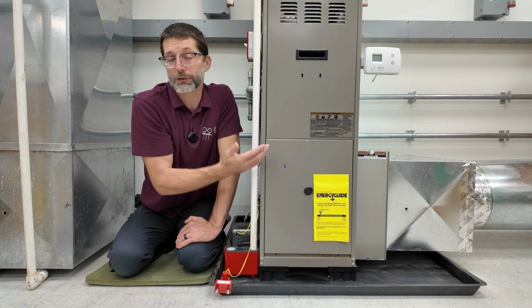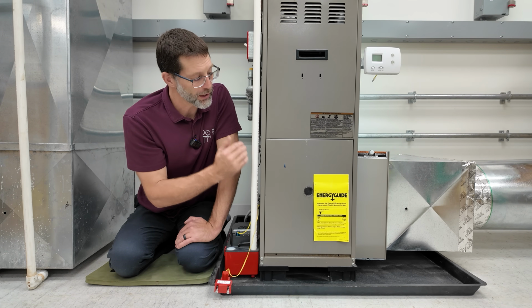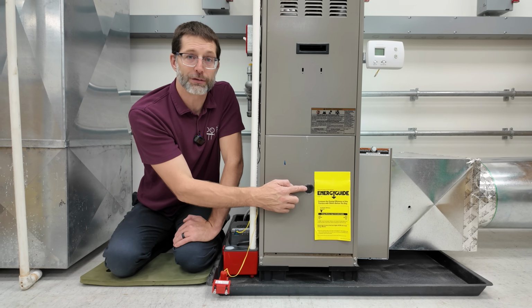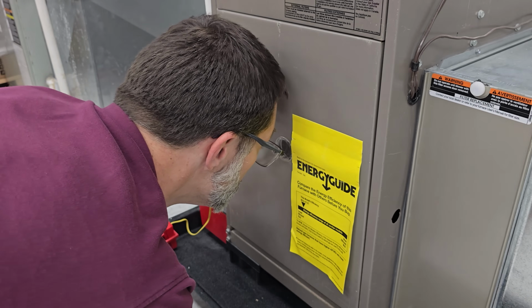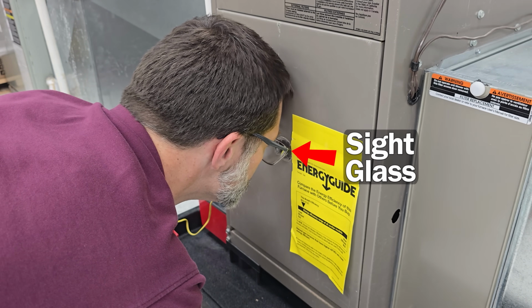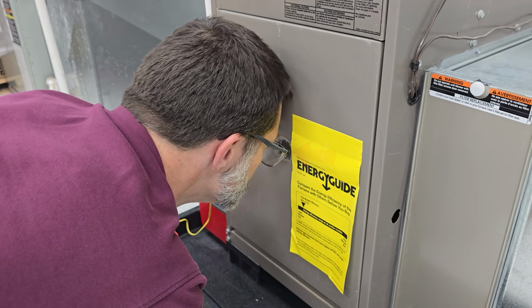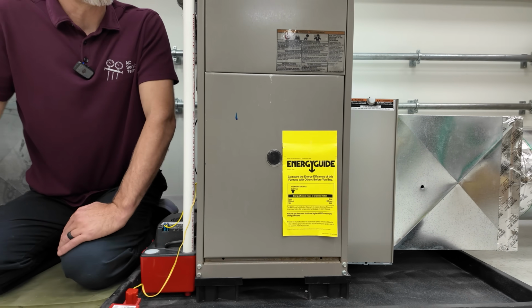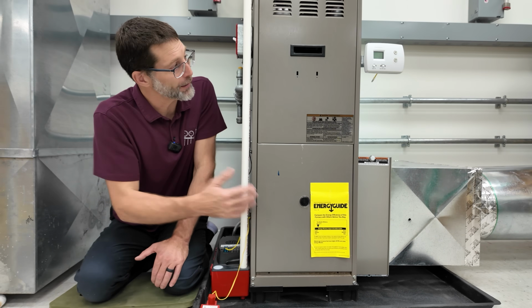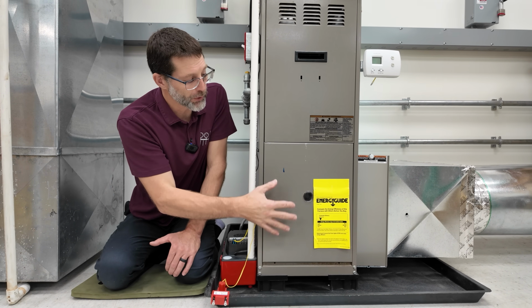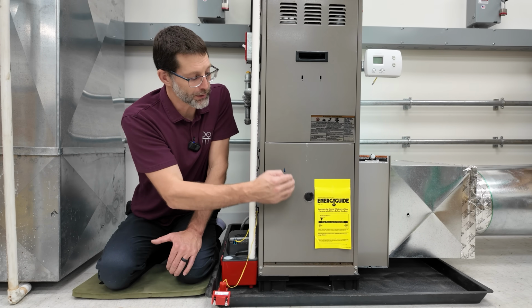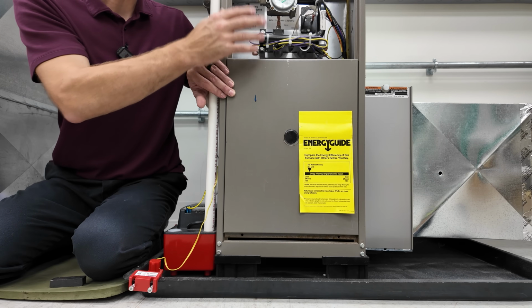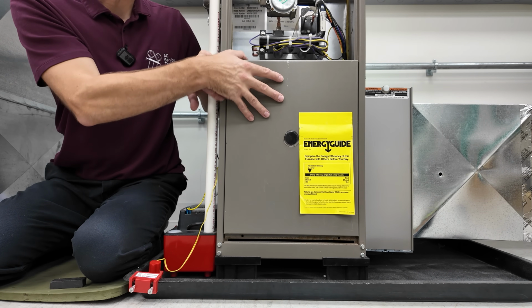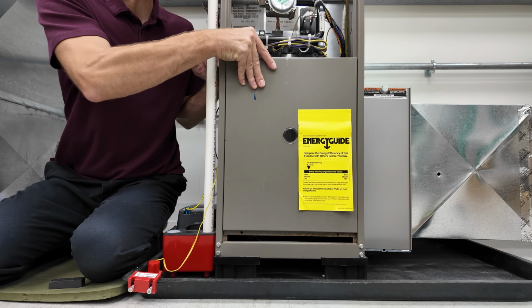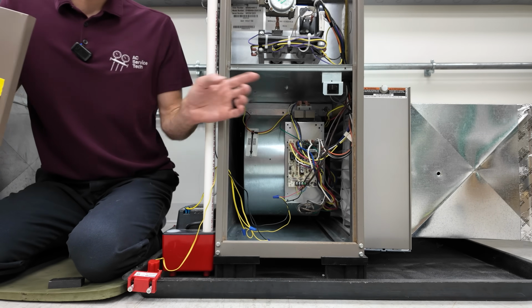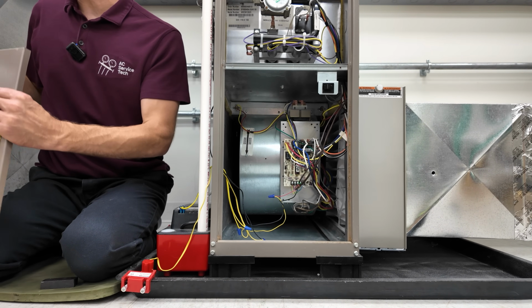We're missing power, right? So the next thing that we're gonna do is come into this sight glass right here and see if we see an LED that's lit, or if there's an error code, some flashing that's occurring. If you don't see any light at all, then we're going to remove this door, then this door, and move our diagnosis into this area right here. Now remember, when you come to the site, you're gonna have a top door and a bottom door. This bottom door on a gas furnace is going to have a door switch. And so that door switch needs to be shut.